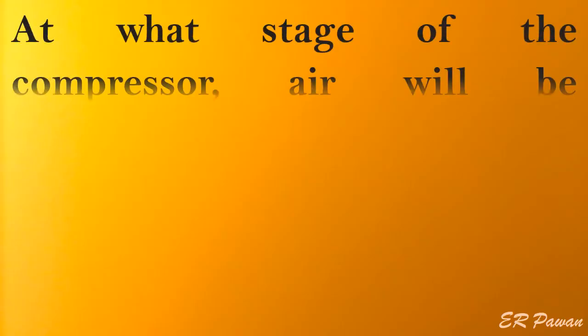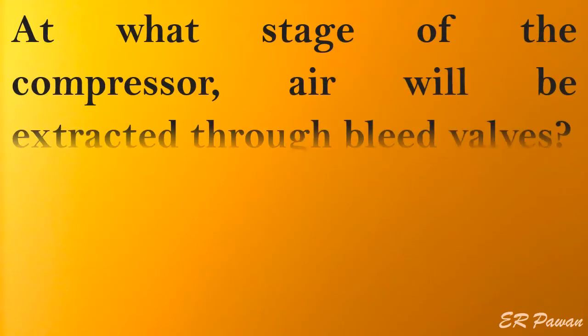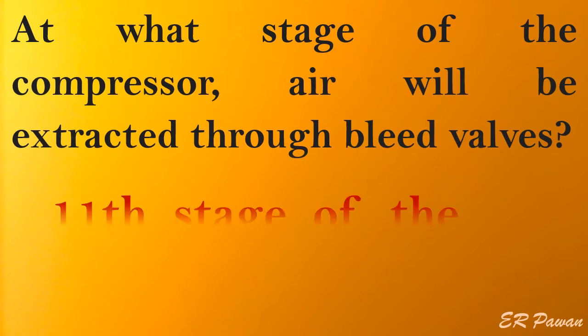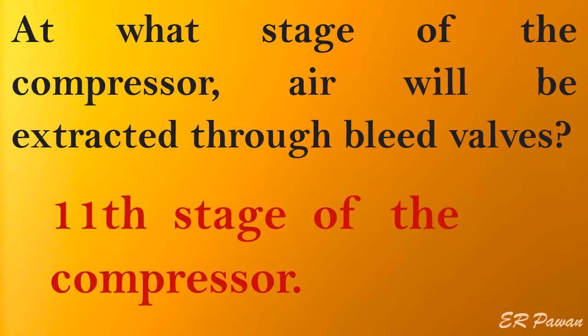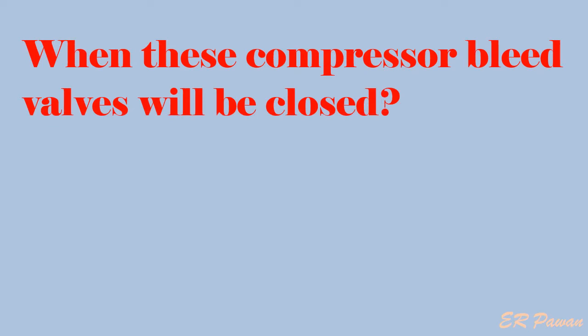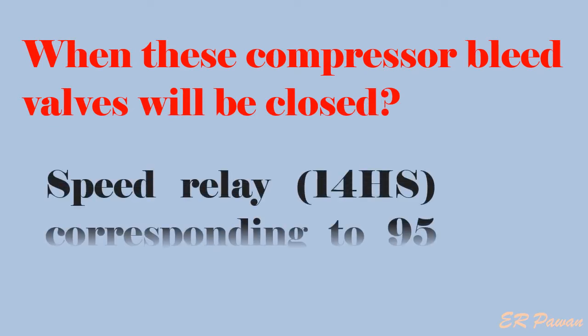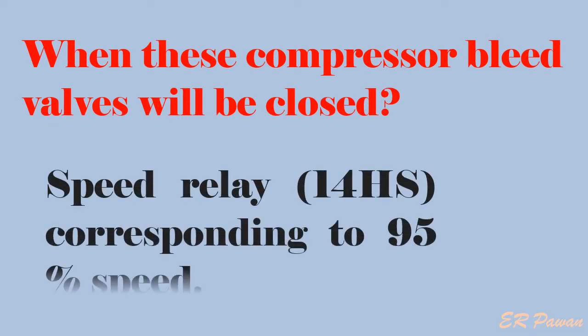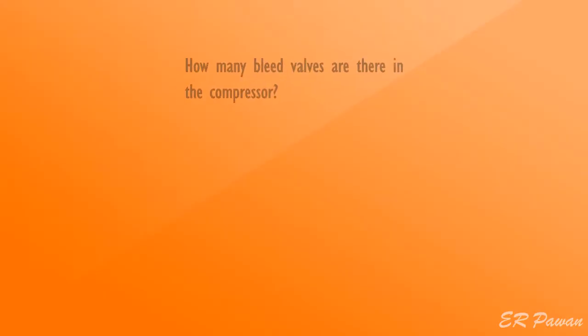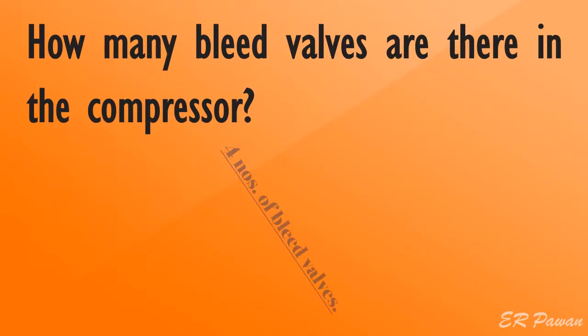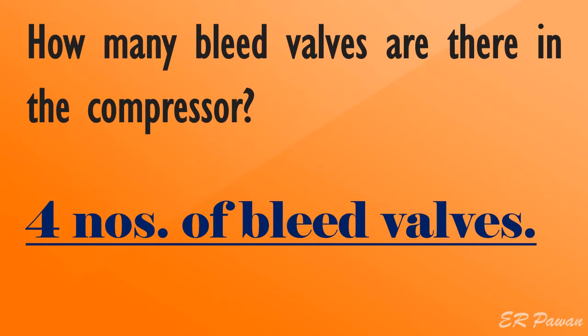At what stage of the compressor will air be extracted through bleed valves? 11th stage of the compressor. When will these compressor bleed valves be closed? Speed relay 14HS corresponding to 95% speed. How many bleed valves are there in the compressor? 4 numbers of bleed valves.